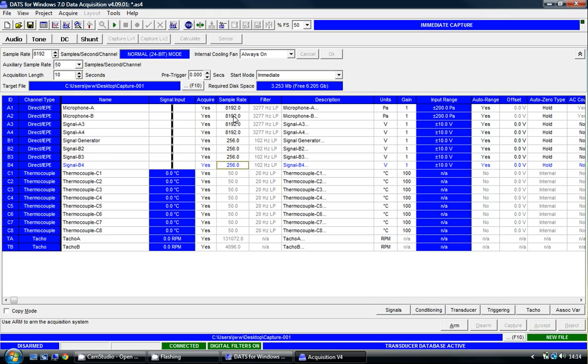8192 samples per second per channel on the first four channels, 256 samples per second per channel on the following four channels, and then the final eight thermocouple channels are sampled at 50 samples per second per channel.